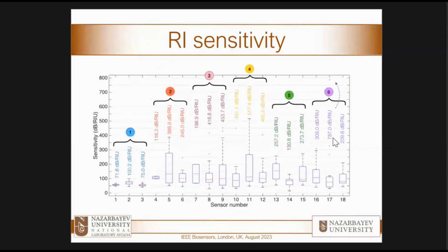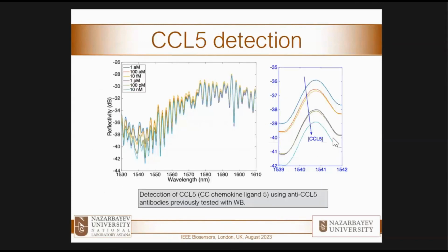And we have studied nearly all the possible fiber combinations, achieving a top sensitivity in the order of 700 dB per refractive index unit, but values around 300, 400, 500 dB per refractive index unit are kind of the norm if you select the right sensing point and the right fiber. Clearly, having a large randomization of the scattering centers, the spectra are random, so you cannot really control them beforehand. But a simple calibration will allow you to find the sensitivity, and it's quite a simple process.